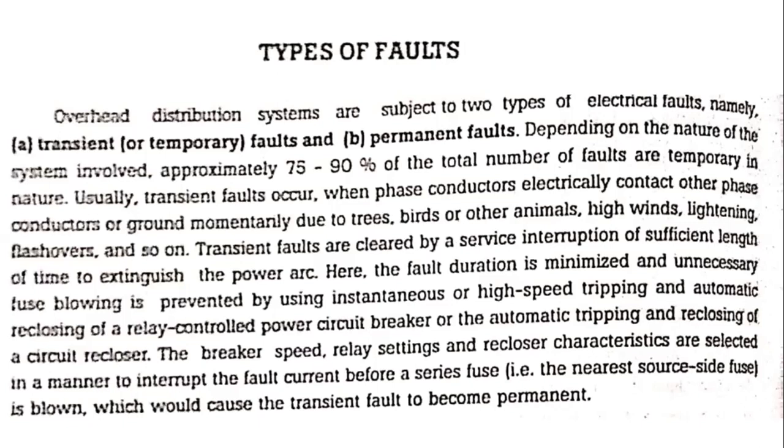By using automatic reclosers, we reduce the temporary faults. Therefore we prevent unnecessary fuse blowings in the distribution systems. Therefore the breaker speed, relay settings and recloser characteristics are selected in a manner to interrupt the fault currents.